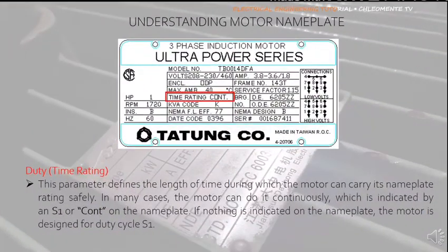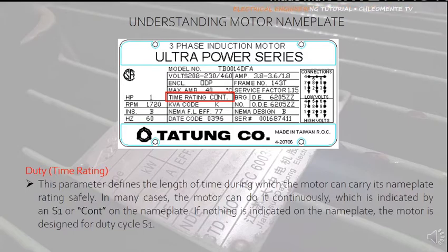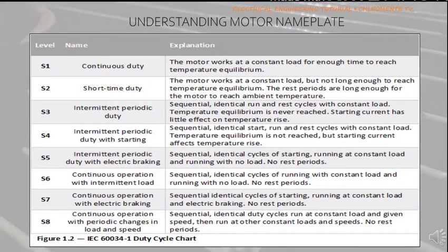Duty or Time Rating defines the length of time during which the motor can safely carry its nameplate rating. Time rating is normally leveled from S1 to S8. In this case, the time rating is CONT, or continuous rating, sometimes indicated as S1, meaning the motor can be operated continuously. If time rating is not indicated on the nameplate, the motor is designed for S1 or continuous rating. S1 or continuous duty means the motor works at a constant load through time until it reaches temperature equilibrium — the point at which no heat transfer occurs.